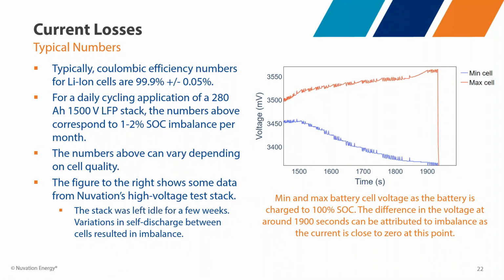For example, this was a system we have in the lab at Nuvation. This is a 1500 volt LFP stack. You can see what happened is it sat for a while, and you get this unbalance between your min cells and max cells. This is showing the difference in those cell voltages as we go to a full charge after the system has sat for a while, and you can see you get quite a delta. This upper one is going up as we get to 100% state of charge in that cell.